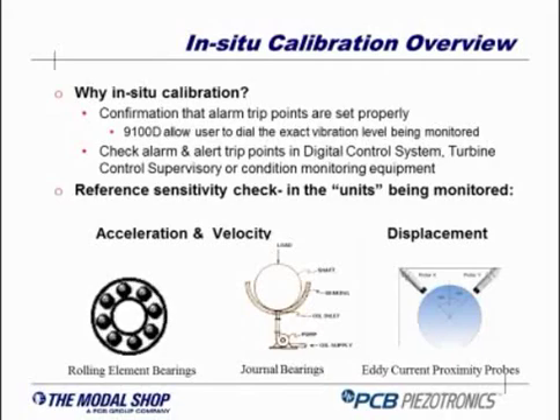One of the benefits of the 9100D is that I can dial the exact vibration level that's being monitored. So if my system is set up to create an alarm when vibration exceeds 3 Gs, I can go on my amplitude dial and dial up 3 Gs. If it's 3.5 Gs, I can dial 3.5 Gs.